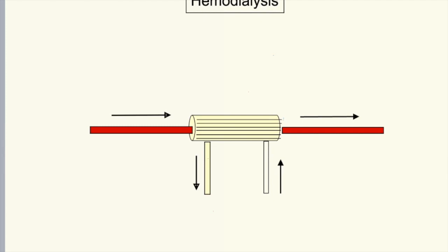In dialysis, the patient's blood flows through the hollow fiber dialyzer in this direction. Dialysate flows through the dialyzer cartridge, bathing the capillaries with metabolic waste products diffusing out of plasma into the dialysate. Note that the dialysate flows in the opposite direction from the patient's blood. This maximizes the concentration gradient between plasma and dialysate as much as possible along the length of the capillary.